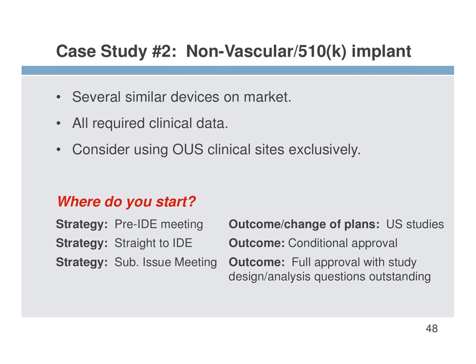And that was a very effective meeting because we really learned what mattered to the FDA. We found out that there was somebody from the Office of Science and Engineering Laboratories that was driving some of these questions. And in fact, one of the senior persons, and not the senior person at FDA, basically looked at us and said, oh, if that's all you're trying to do, then just change your label and be fine with it. We'll be fine with it. So that was a great meeting because we really did get some questions answered.